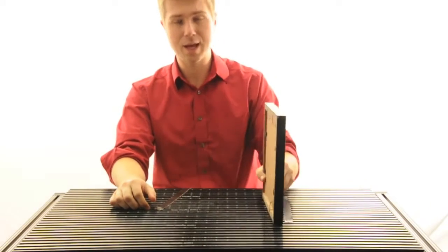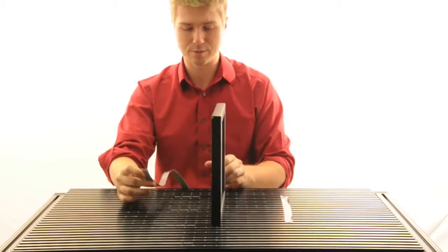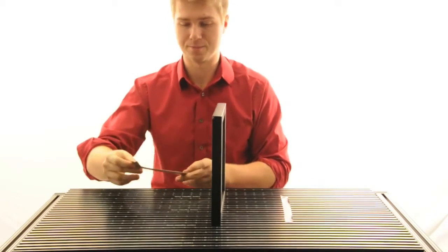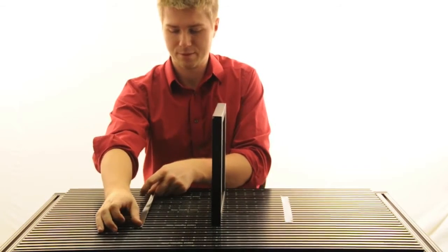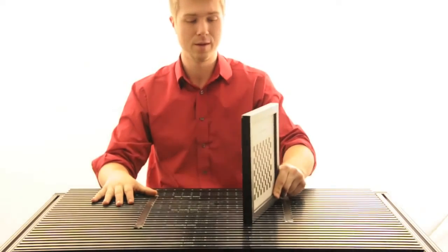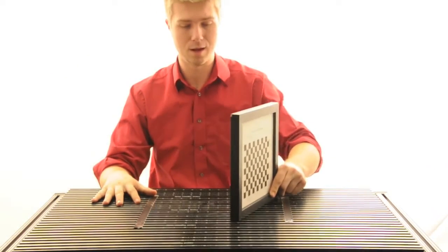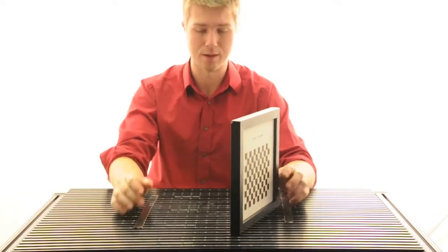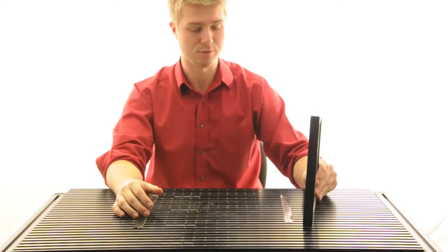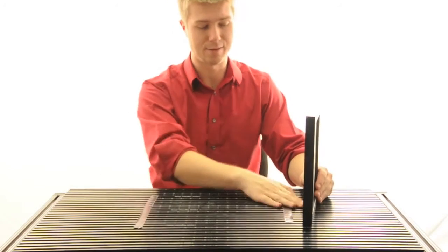The depth, however, so the depth of field, is going to be set by the user. That depth of field is set by where you move this calibration board inside of your scanning window. So if you move it closer forward, then it's going to be at a set forward position.